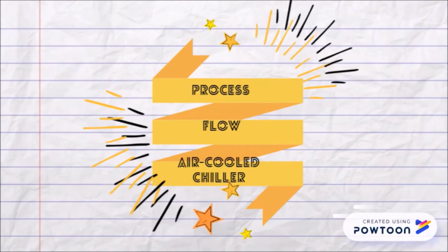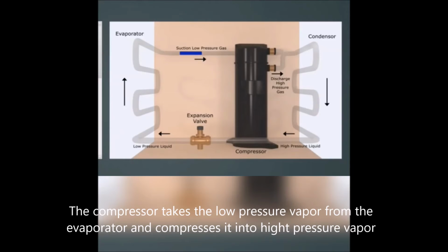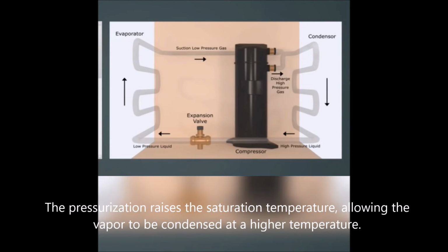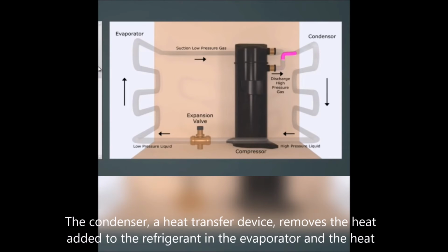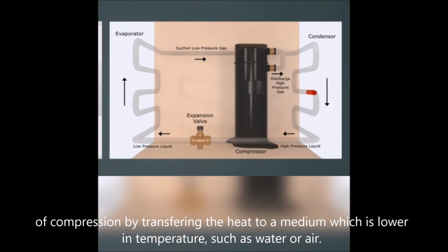Process flow air-cooled chiller. The compressor takes the low-pressure vapor from the evaporator and compresses it into high-pressure vapor. The pressurization raises the saturation temperature, allowing the vapor to be condensed at a higher temperature. The condenser, a heat transfer device, removes the heat that has been added to the refrigerant in the evaporator and the heat of compression by transferring the heat to a medium which is lower in temperature, such as air or water.